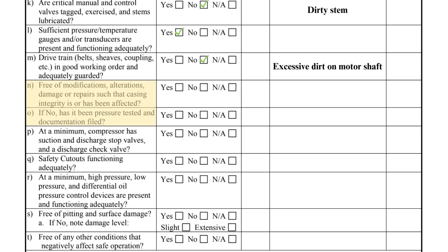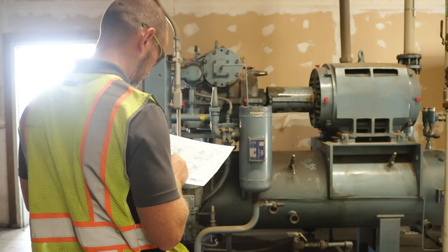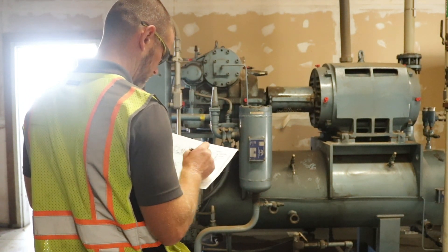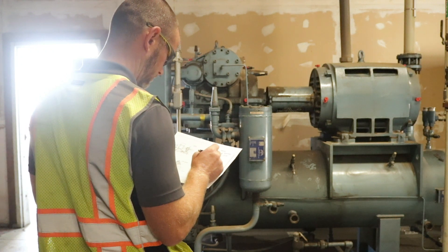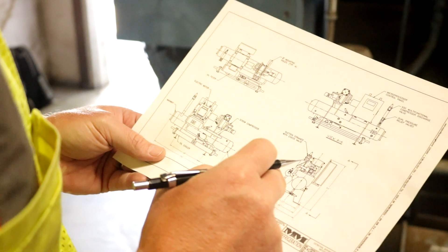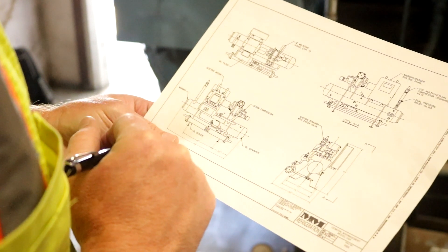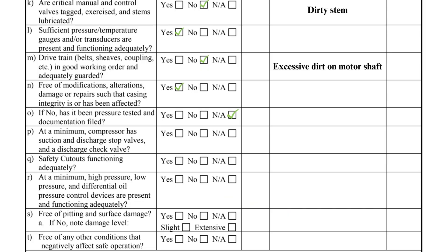Item N asks if the compressors are free from any modifications, alterations, damage, or repairs. While this cannot be conclusively answered without the original compressor drawings, the inspector can still look for indications that alterations have occurred. If there is evidence of equipment modifications, the appropriate checkbox in item O must be answered.